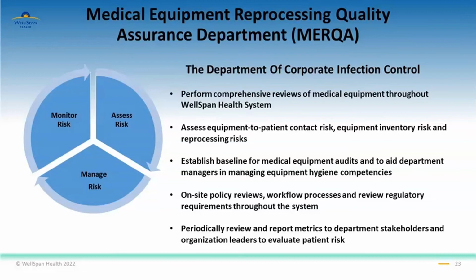Secondly, we look at the equipment's location risk. The assessment involves a process for analyzing the critical areas where medical equipment is used and categorizing these locations by a level of patient acuity. In review of these locations, MERQA depends on the WellSpan's biomedical equipment department to assess where the equipment lives and how it moves throughout the facilities in audit. This assessment can be done either by an electronic equipment database, a surgical instrument tracking program, or by equipment tracking devices such as radio frequency identification, or RFID tags.